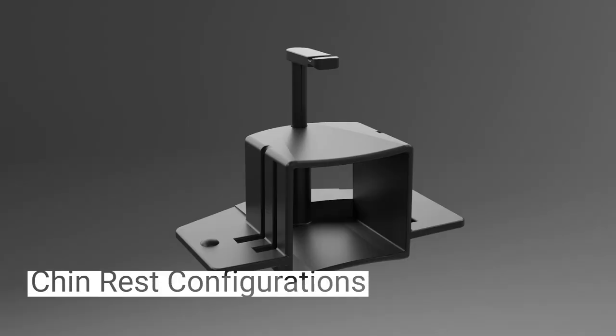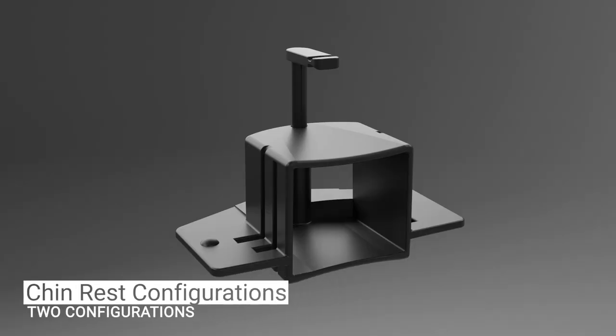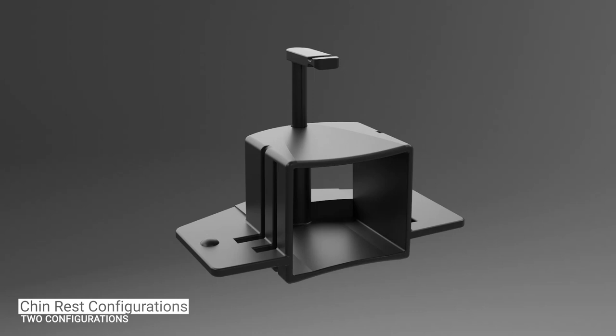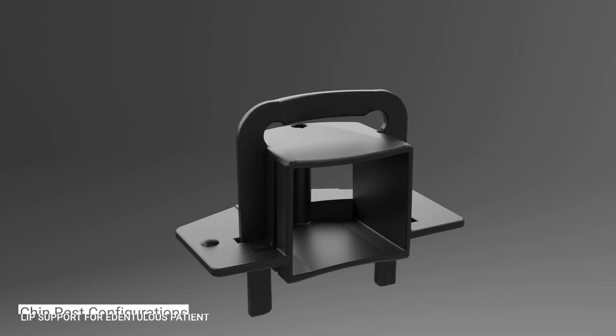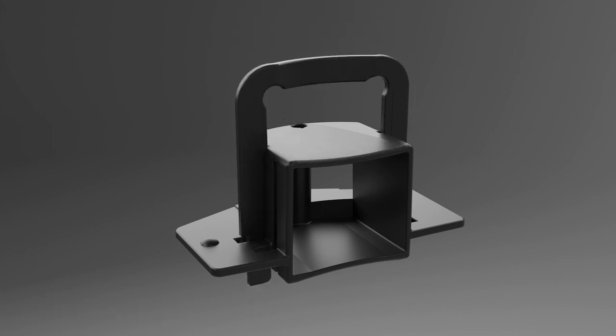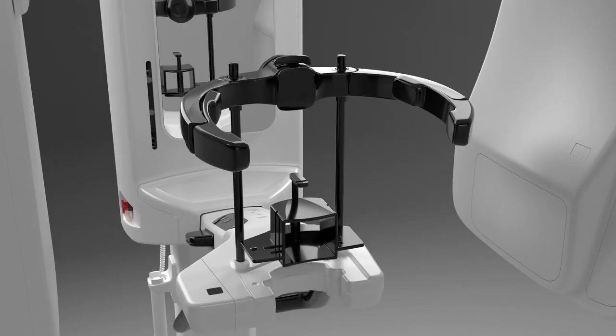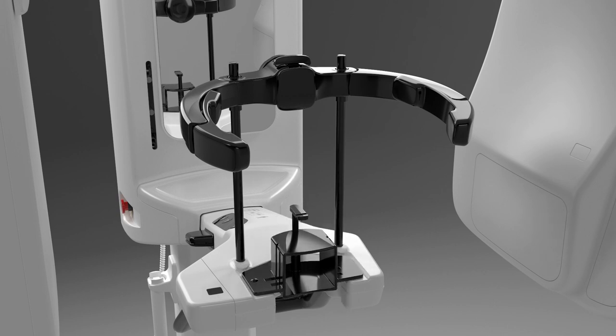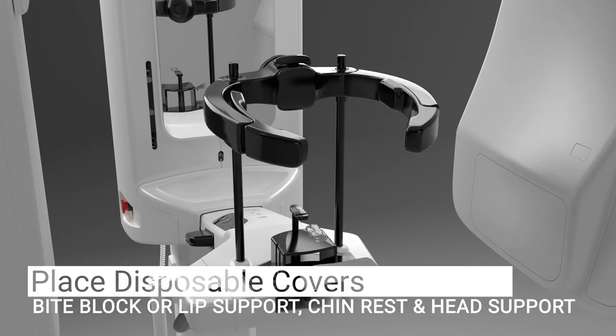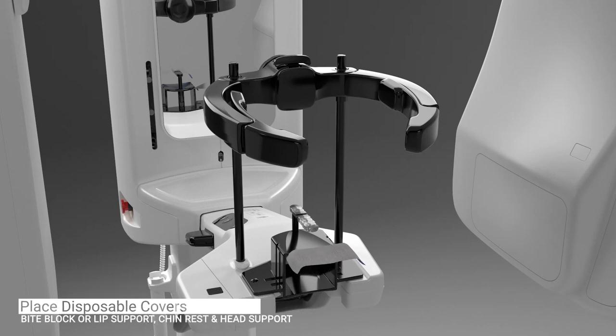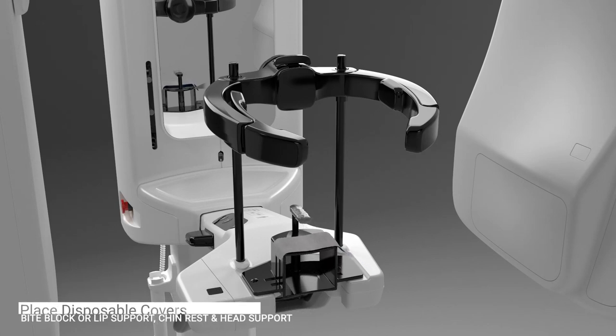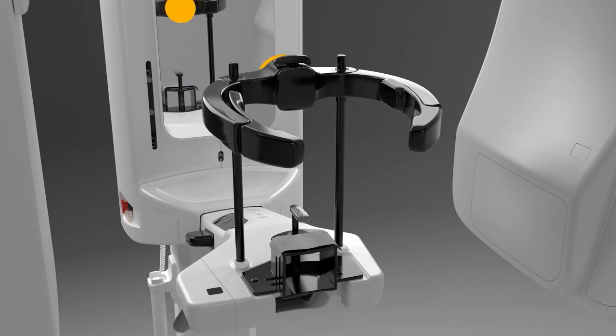There are two chin rest configurations that can be used when acquiring a 2D panoramic image: standard panoramic and pediatric panoramic. Both require the bite block and chin rest, except for edentulous patients that require the use of the lip support and chin rest. Pre-configure the chin rest and place it into the system. Place disposable covers on the bite support or lip support. Open the patient head support, turning the knob on the head support counterclockwise.